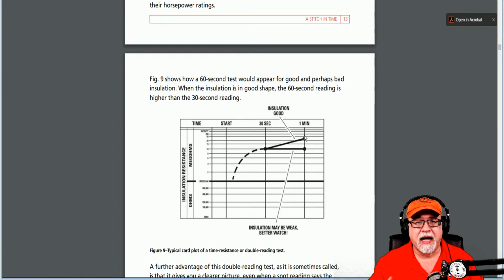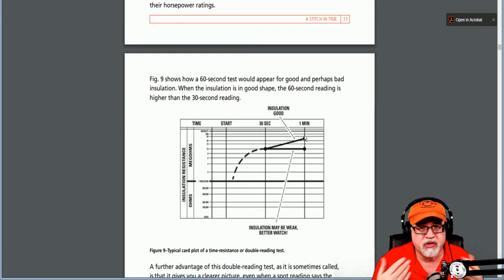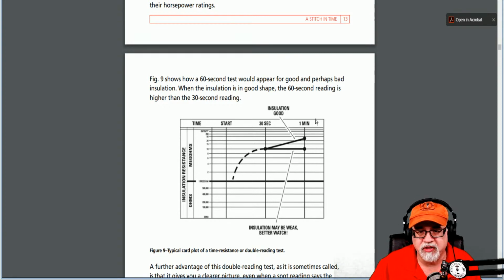Now, this is better than the spot test, which is just a 60-second, alone, 1 minute test, because you don't get the real picture of the rise, okay? And you get past what we call that capacitive point, and it starts to go up. So spot testing at 60 without any other observation is not my recommendation. Do what you want. But if you're going to do this, I want you to do a 30 and 60 second, or 30 second and 1 minute, and that would be a dielectric test. Okay, so that's a dielectric absorption test.